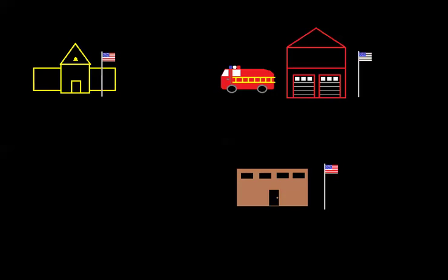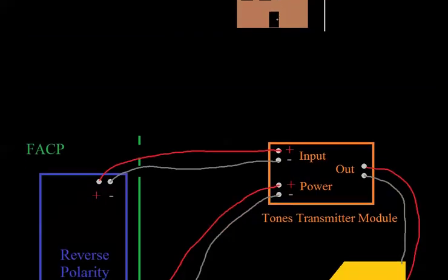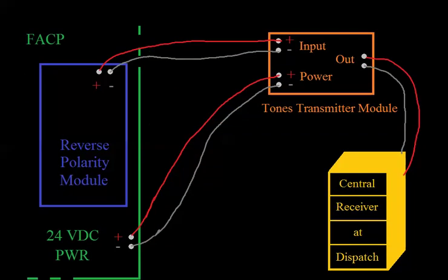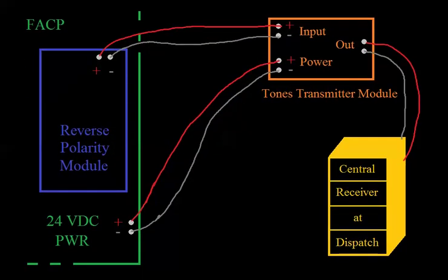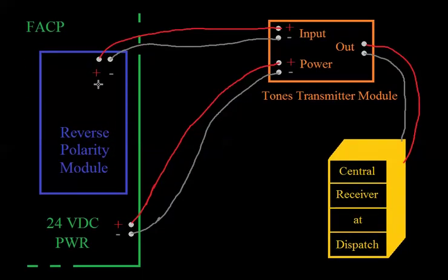And I mentioned that it's not used very commonly anymore. And one of the big problems with it was, if you remember, I said that in a normal state, the reverse polarity module, which is sent to the Tones transmitter module, would put out a positive 24 volts. And then in an alarm state, it would go negative.